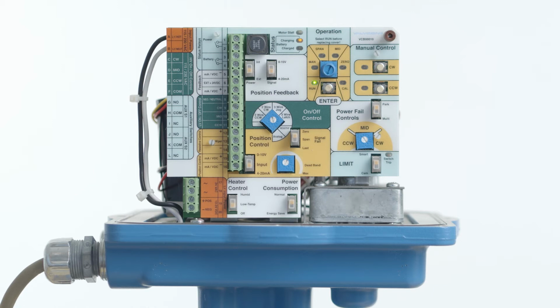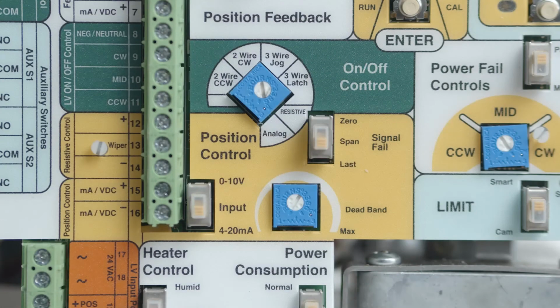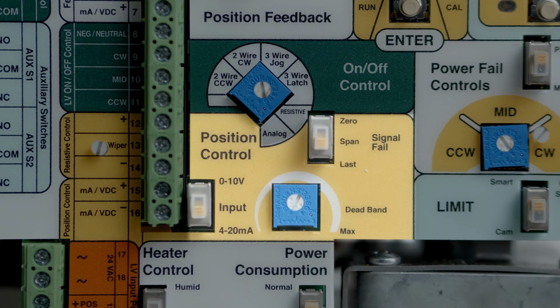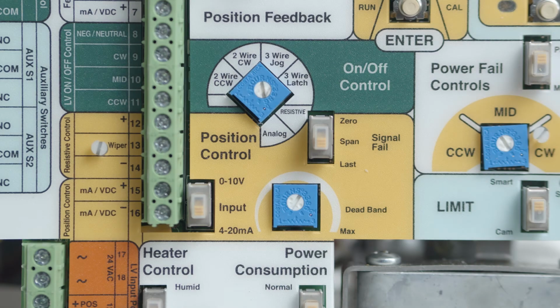When using the analog position control mode, the board can be set up to respond to a loss of control signal when external power is still present. The board can be set to drive the actuator to the saved 0, typically the minimum signal position, the saved span, typically the maximum signal position, or to fail in place, the last position the unit was in when the signal was lost.